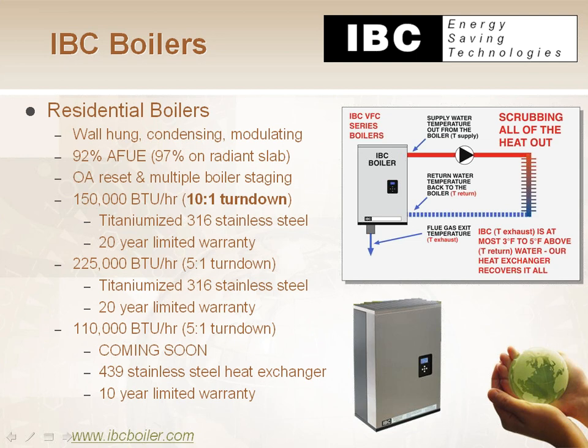One of those is on the 150,000 BTU size. He has a 10-to-1 turn down, which means I can go from 150,000 BTUs down to 15,000 BTUs, or from 100% to 10% if you want to think of it that way. So that allows me to accommodate much smaller zones than I might on another project. So if I want to micro zone the system and have very small zones like a bathroom on its own zone and things like that, this boiler will do a very good job of that.